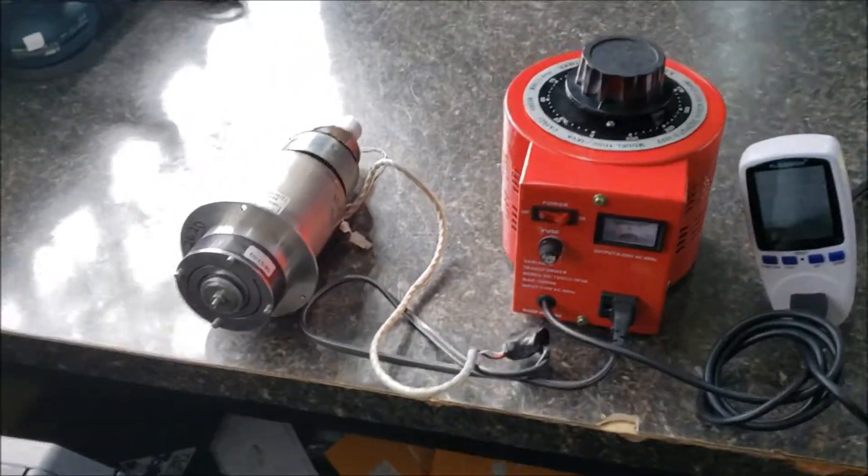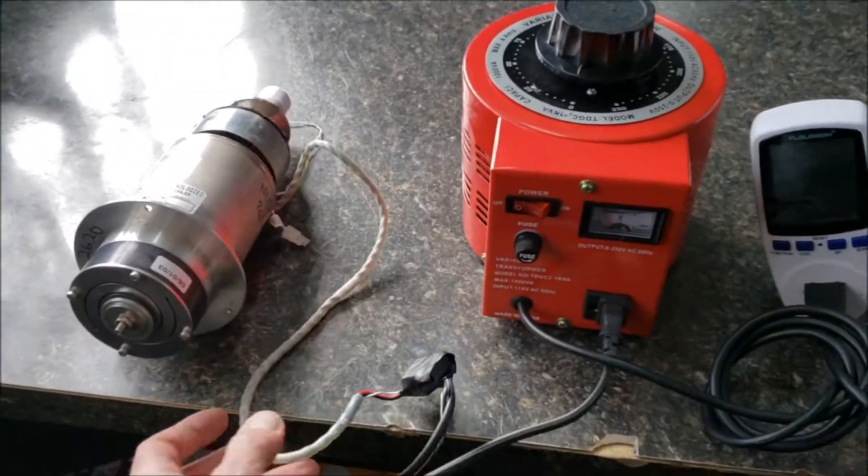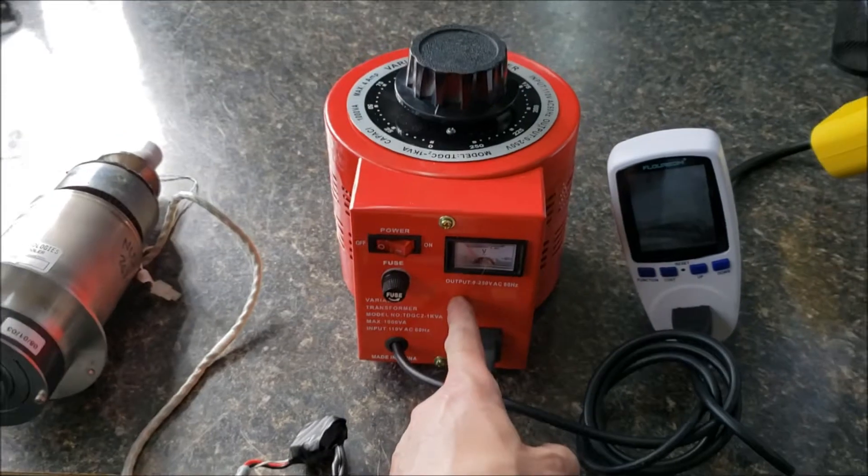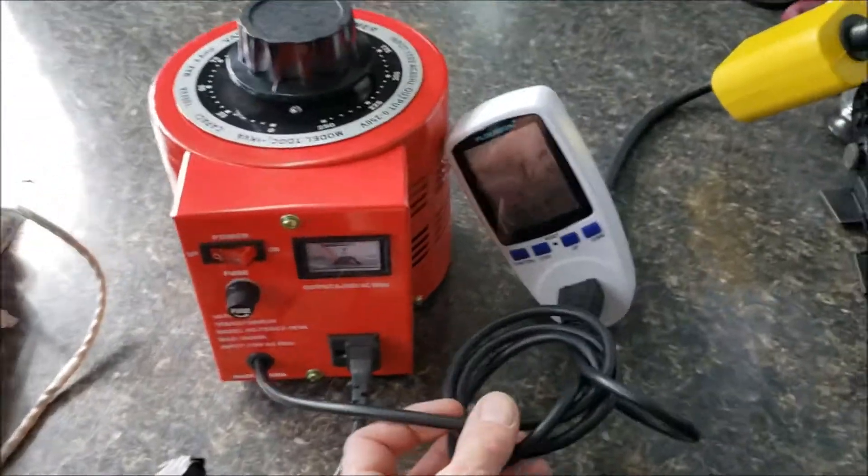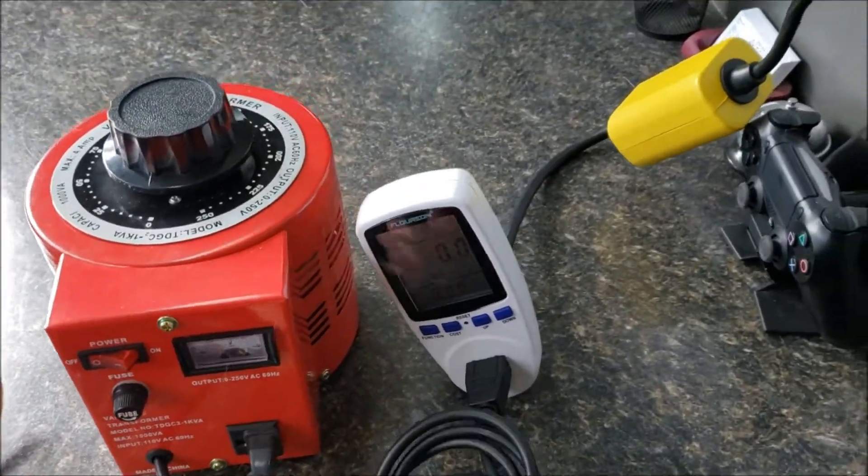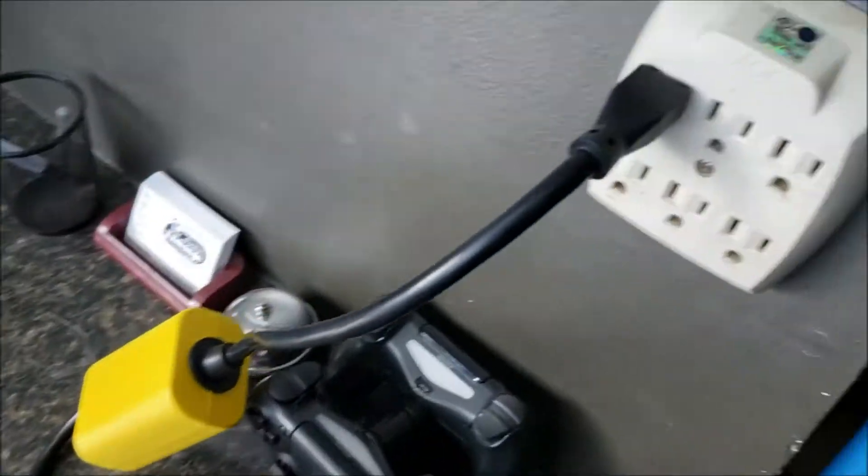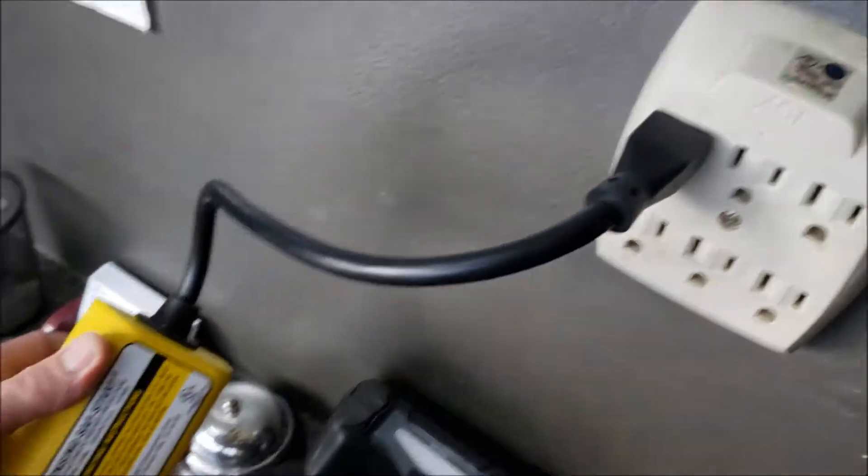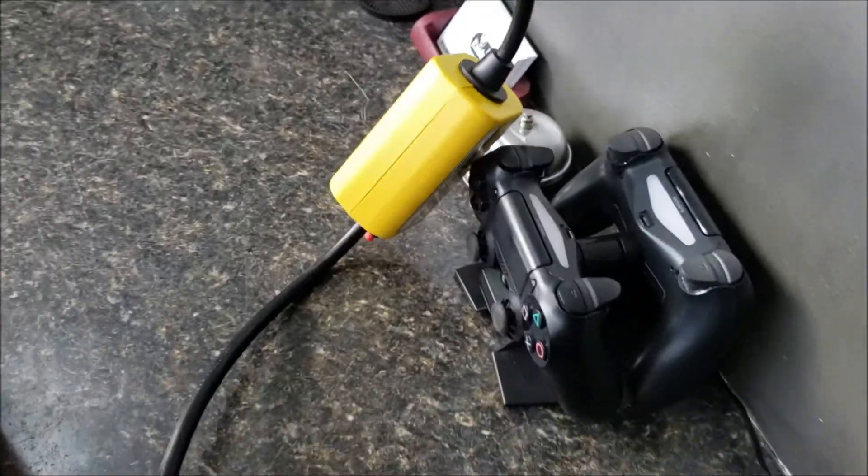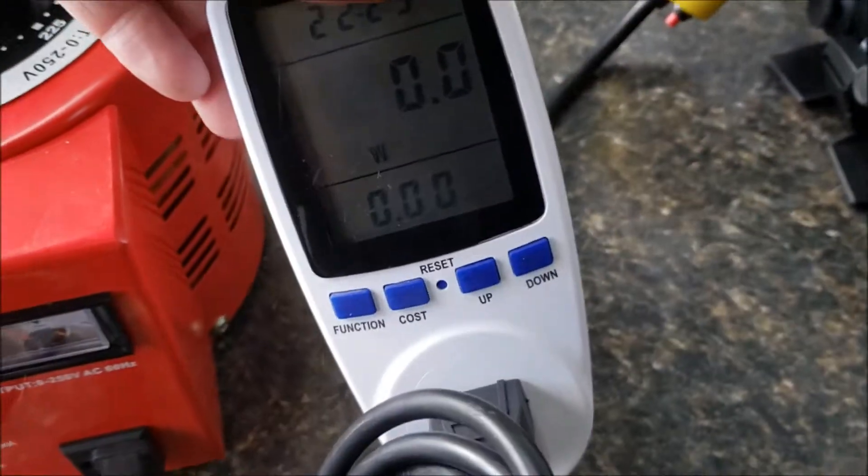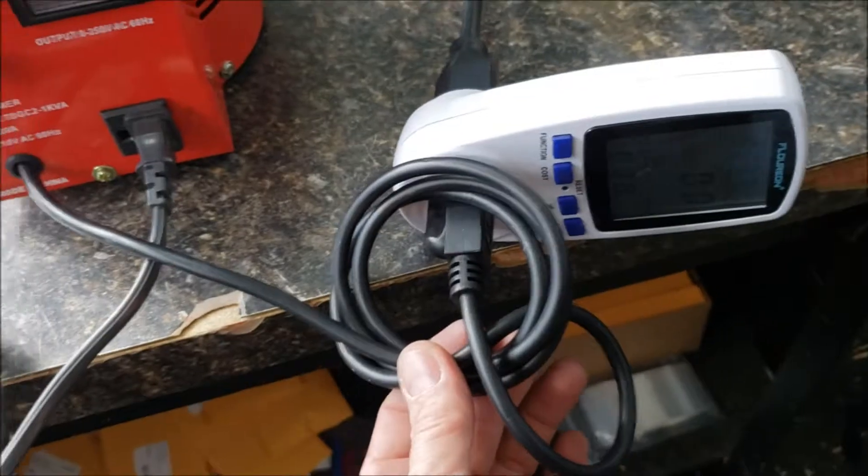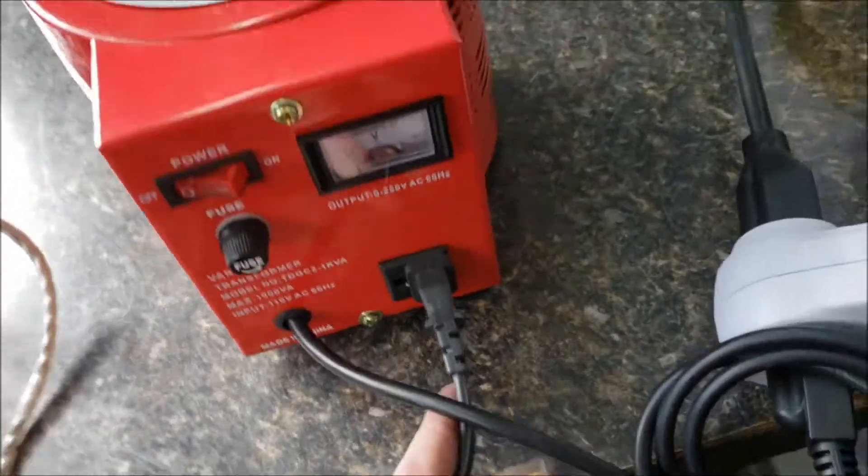Okay, you'll notice the cryo-cooler is plugged into the Variac. The Variac is plugged into the wattage meter. Wattage meter is plugged into the sensing safe start. Okay? Sensing safe start to wattage meter to Variac and the Variac to the cryo-cooler.